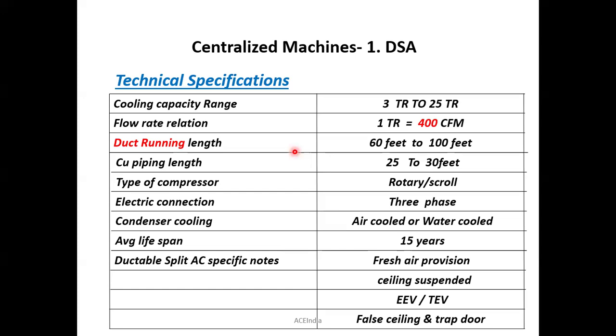Then we studied that in these centralized machines, we can see duct connections. But there is a limitation to the duct connections also, which is the running length. That means from a single machine, what should be the probable max running length of a duct? Generally, for a DSA, that means a ceiling suspended unit, the duct running length should be considered nearly 60 feet to 100 feet. Okay, 60 feet to 100 feet. Then, as I mentioned before, the copper piping length is still common, that is 25 to 30 feet itself. And generally, they use a rotary or scroll compressor.